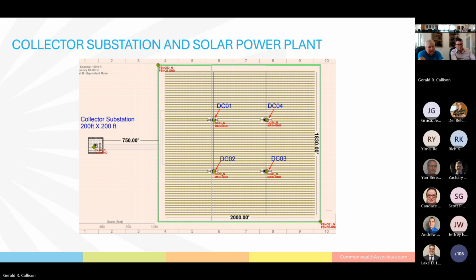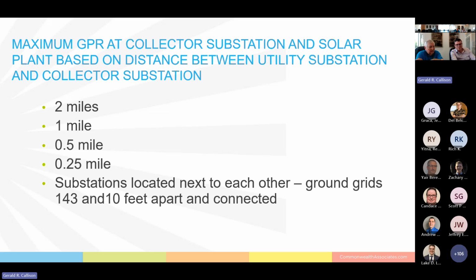Those nodes are going to be important, and keep in mind where those are located. And the ones that I forgot to point out are the fence nodes. And this is to determine what the voltage is on the fence at those 2 corners. So what we're going to do is determine what happens when the maximum ground potential rise fault occurs. The substation and the collector station are moved closer and closer together for that fault. And then we're also going to look at it when the substation is 143 feet apart and 10 feet apart, and the substations are connected together through their ground grid.